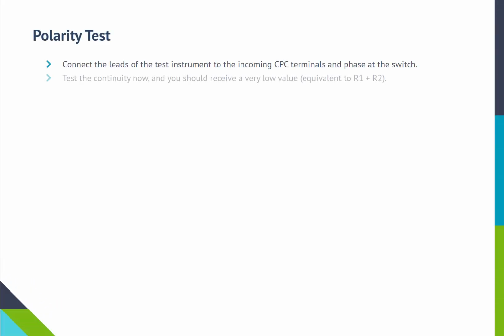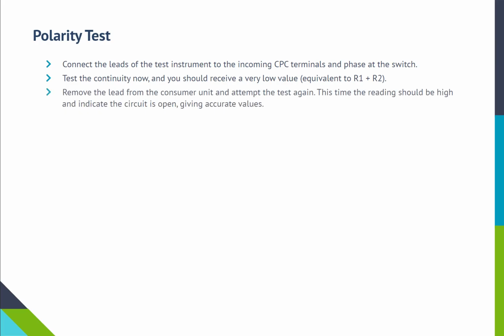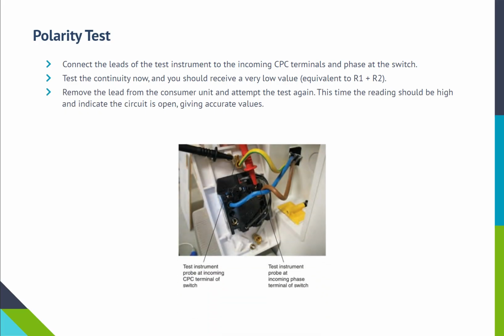Connect the leads of the test instrument to the incoming CPC terminals and phase at the switch. Test the continuity now, and you should receive a very low value, equivalent to R1 plus R2. Remove the lead from the consumer unit and attempt the test again. This time the reading should be high and indicate the circuit is open, giving accurate values.